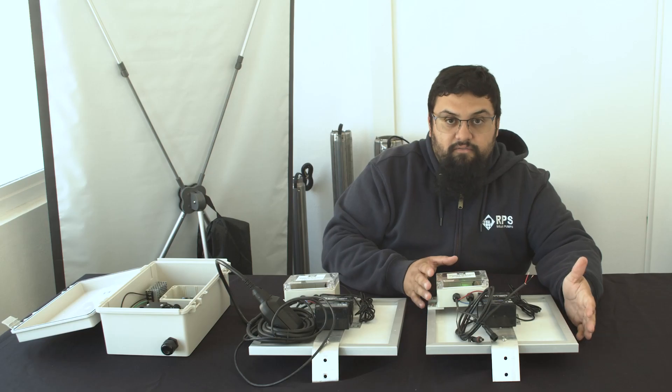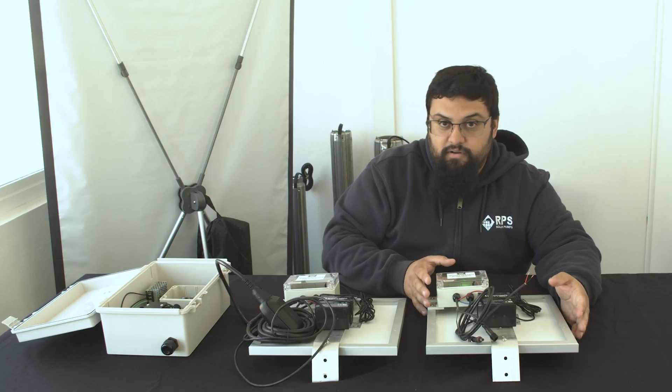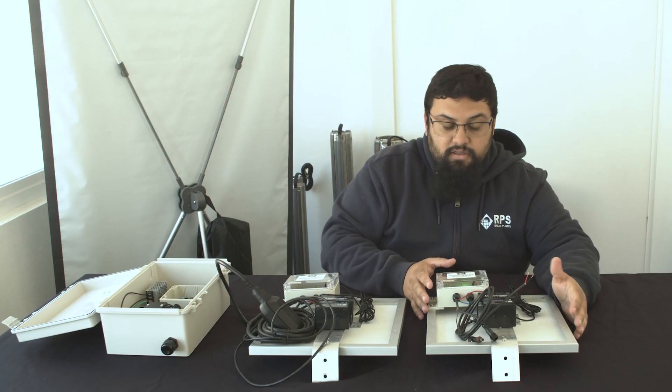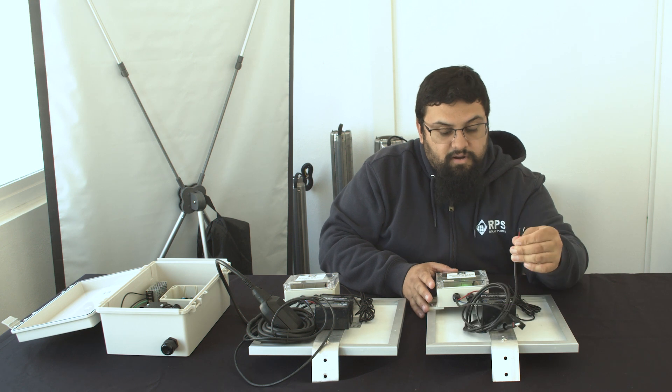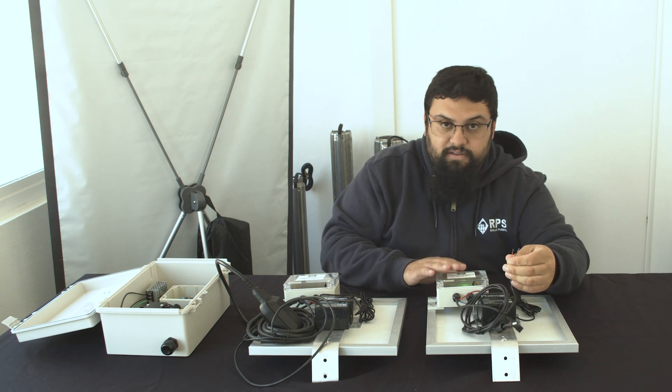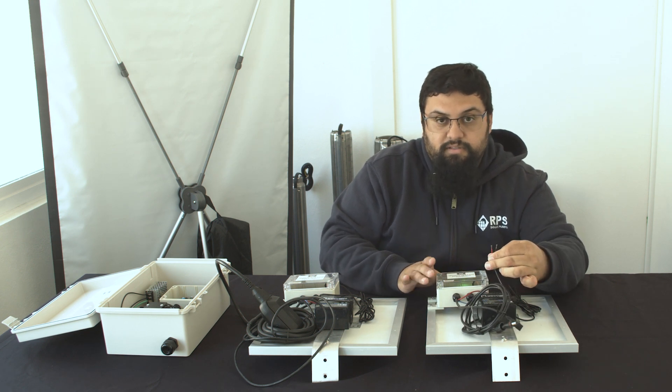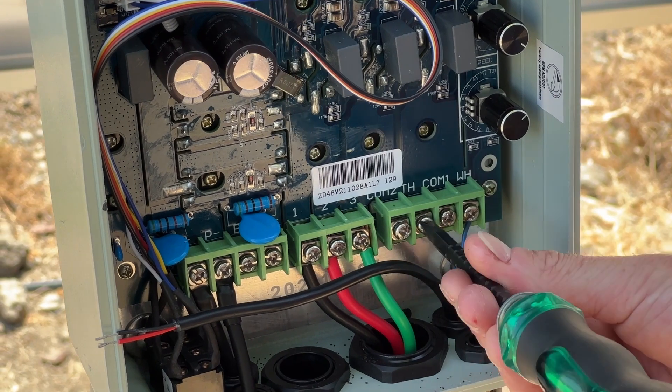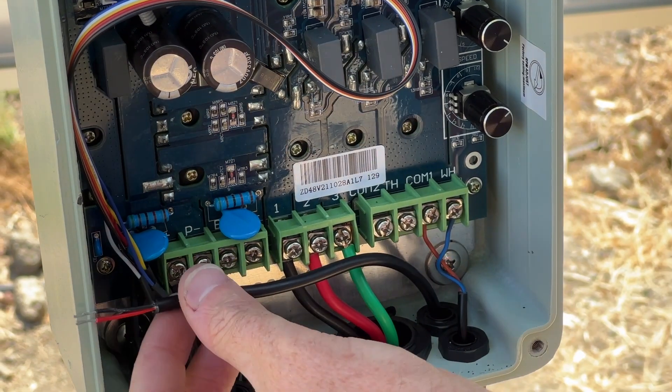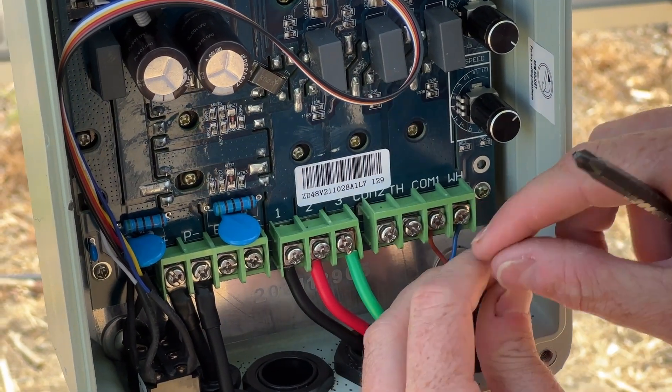If you have one of our RPS 200 to 800 models, you will take your two wires coming off of the receiver and wire them up into COM2 and TH. This is normally where you would wire up your tank full sensor.